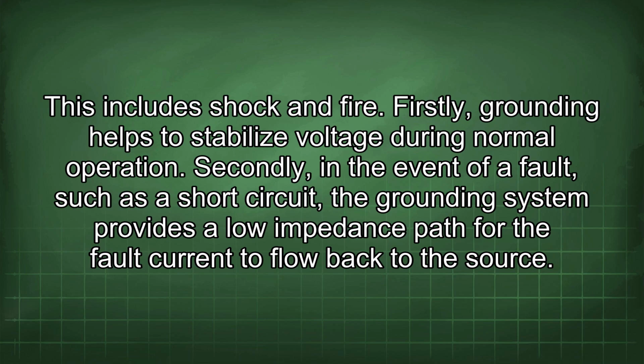Firstly, grounding helps to stabilize voltage during normal operation. Secondly, in the event of a fault, such as a short circuit, the grounding system provides a low impedance path for the fault current to flow back to the source.